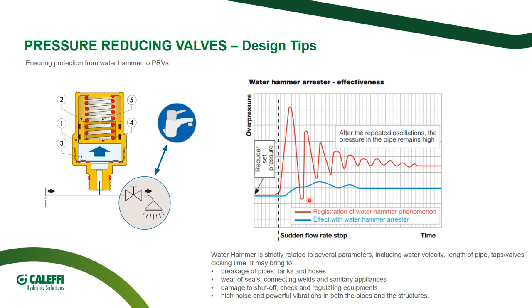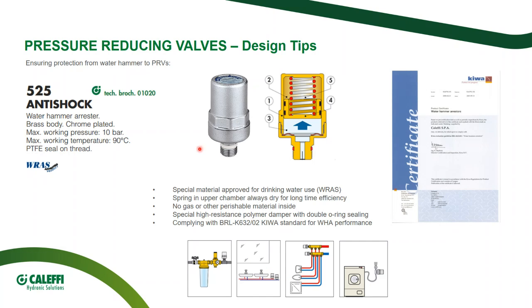And this water hammer is caused by the sudden closure of some devices of the system, like lever-type taps and solenoid valves. And the quicker the closing time and the bigger the system, the higher the overpressure caused by the water hammer. That's why the water hammer arrester has to protect the system. It has to be installed in a peripheral position, and it also has to last for several years. That's why the Caleffi water hammer arrester is not a gas pre-charge type, but we decided to design a stainless steel spring inside a dry chamber that the water cannot reach, in order to ensure the maximum possible efficiency also over a long time period.